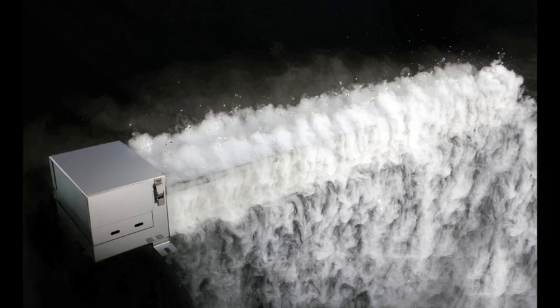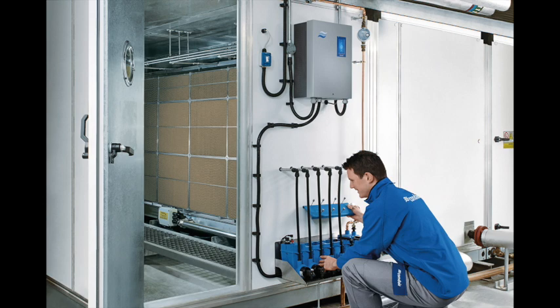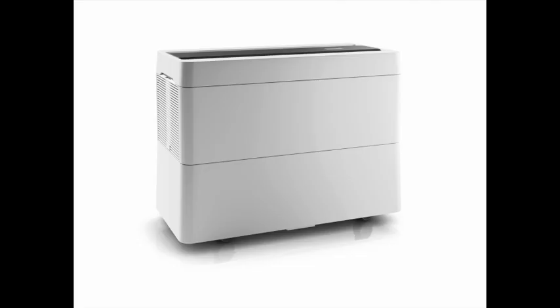And lastly, evaporative humidification, where moisture is evaporated directly from a wetted surface. These are a great option for AHUs if space allows. Any cold water humidifier will typically take up a bit more space inside the duct than a steam humidifier's steam pipe. So for AHUs, the duct section length can be a deciding factor in the product selection. Oh, and commercial mobile humidifiers tend to use evaporative technology too. They can typically deliver a few kilos of humidity per hour and are useful for places like art galleries or small offices.